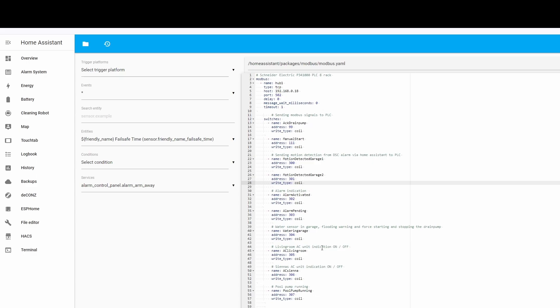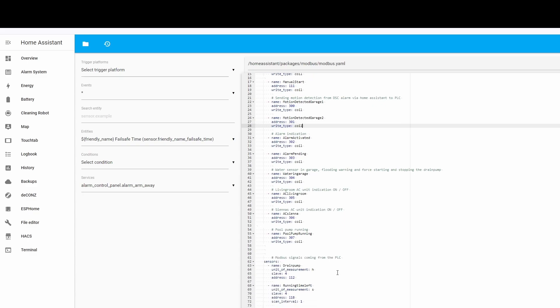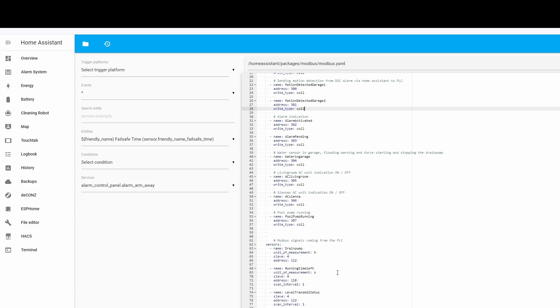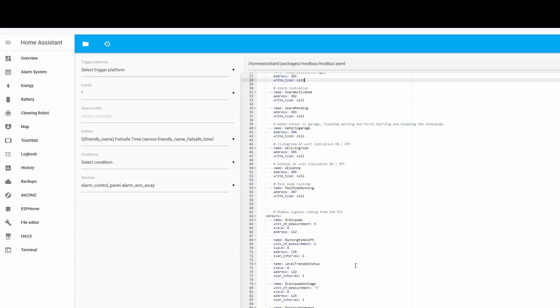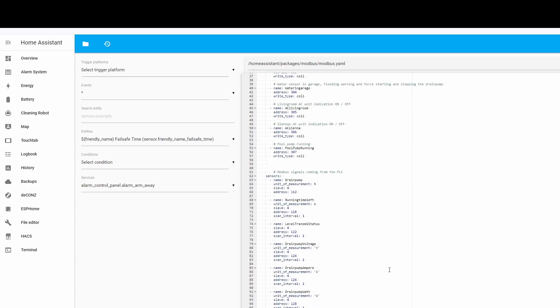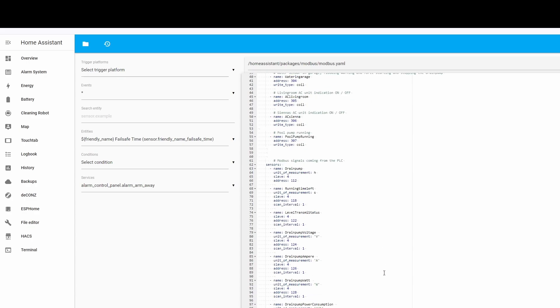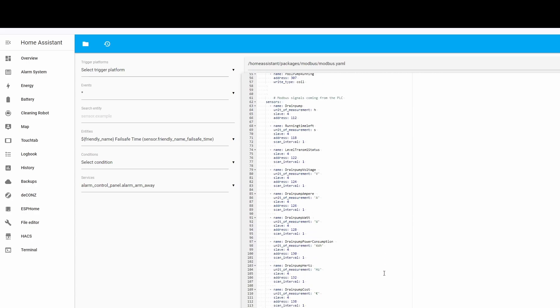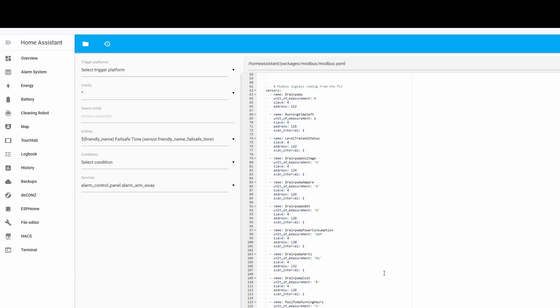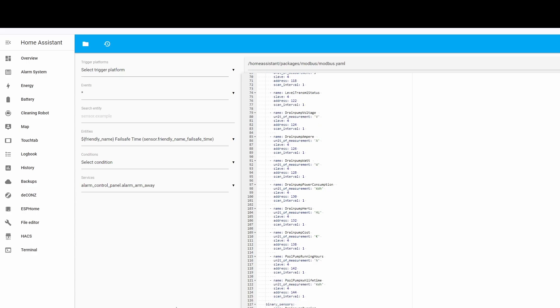The initial thought was to control the pump from the PLC or have the PLC as a middleman between Home Assistant and the pump. I'm also sending Modbus signals from the PLC - if the pump is running, how much time is left, my level transmitter, consumption, hertz, you name it, you can get it.